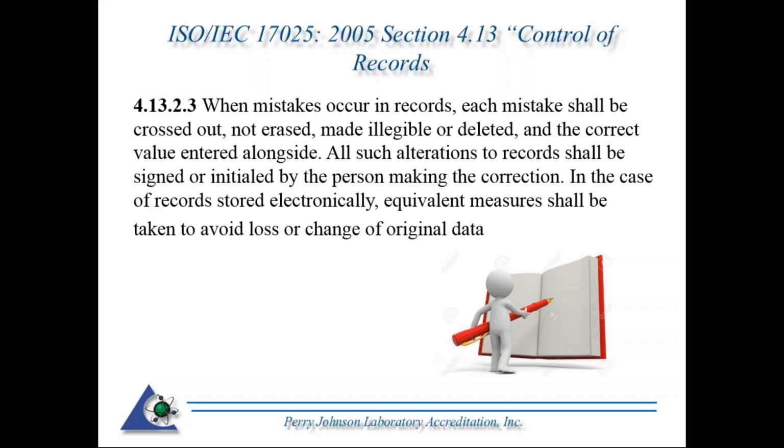So handwritten records, for example, if you are performing a test or calibration, and let's say you have a logbook that's associated with an analytical balance where you have test weights, Class 1 test weights that you use to check the balance, and you have predefined limits set where you'll qualify the equipment in use. Quite often I'll still see those things hand recorded.